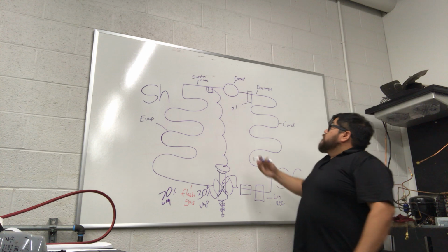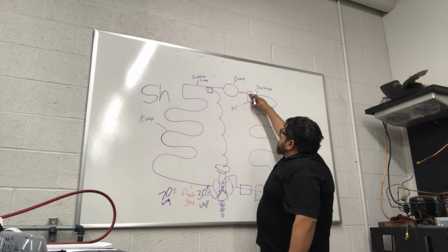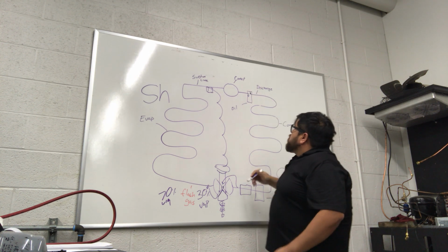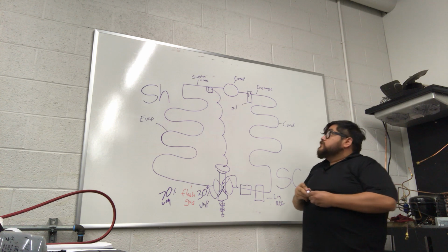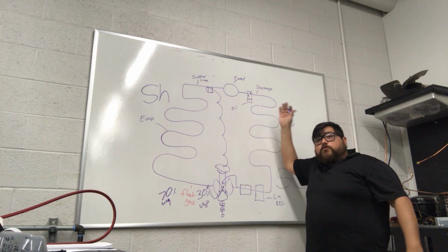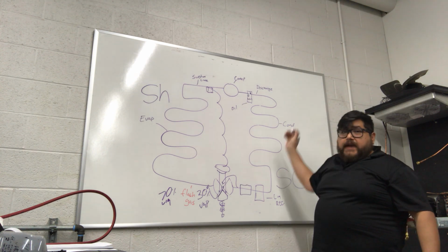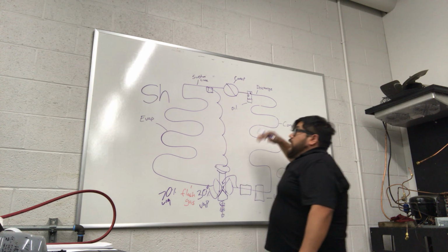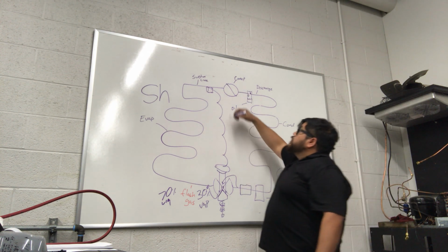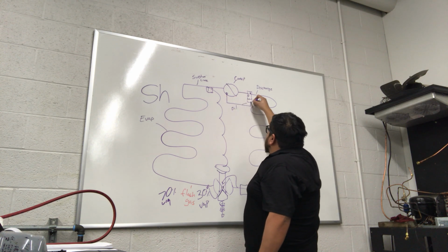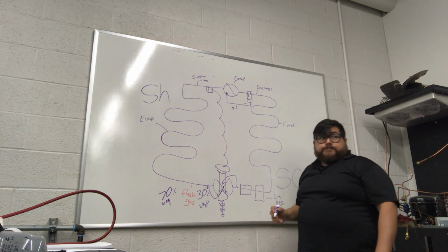So the way we catch oil is, we separate this pipe, we have an inlet, it'll shoot the oil down, and then we have sort of an outlet. So any oil will collect at the bottom. Cool, we collected the oil, now what do we do with it? How do we get it back into the compressor? Well, in the compressor, just like our system, we have a high side and we have a low side. So on the compressor low side, we're going to install a port and connect it to the bottom of our can.